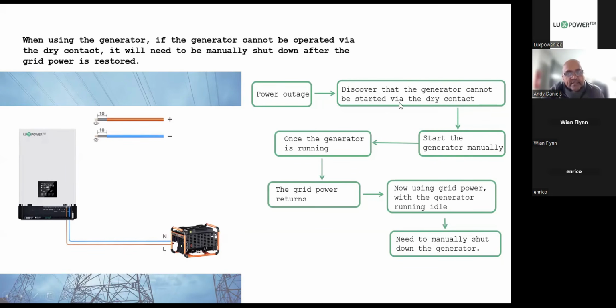It's because our inverter will monitor the power input. So your generator voltage regulator has to be running or serviced or working properly, because we're looking for a voltage range and we're looking for a frequency range. I saw somebody commenting this morning that the generator is running, is putting out 212 volts and 42 hertz, and they can't see anything on the AC, on the generator input. Obviously the relay won't close because the frequency is too low. Remember that when the generator is running through there, the inverter doesn't modify the sine wave of the generator input, it copies it. So it's got to be clean power coming in, because that power has to run the load as well as run our AC side on the inverter, convert it to DC to charge the battery.